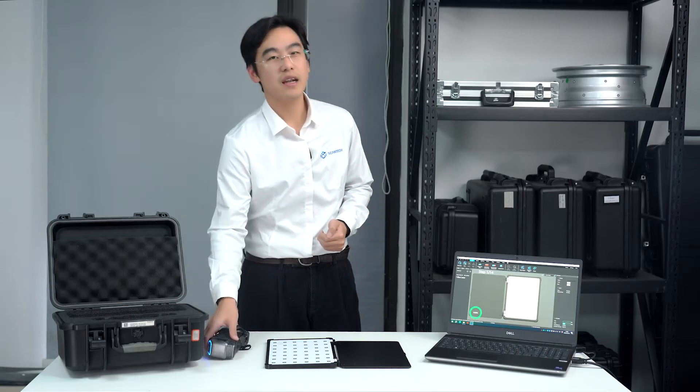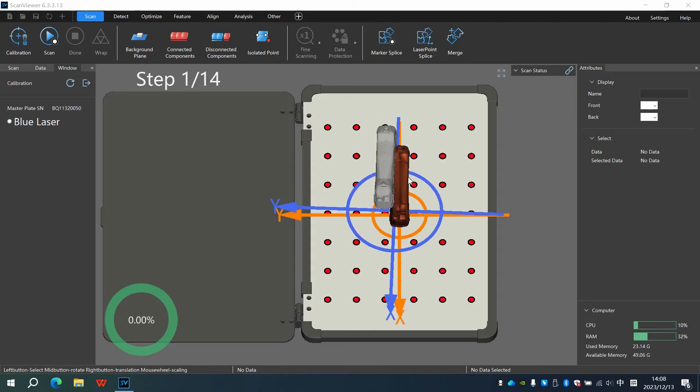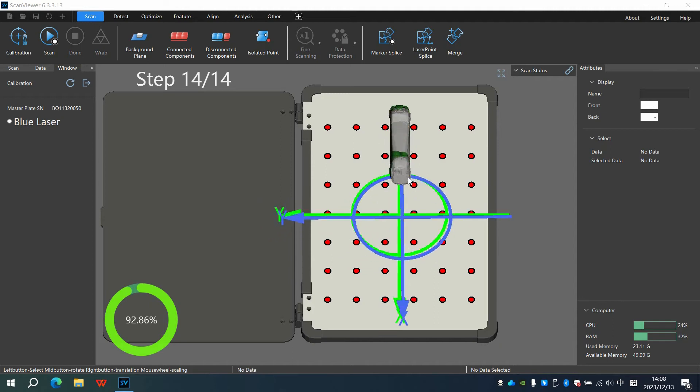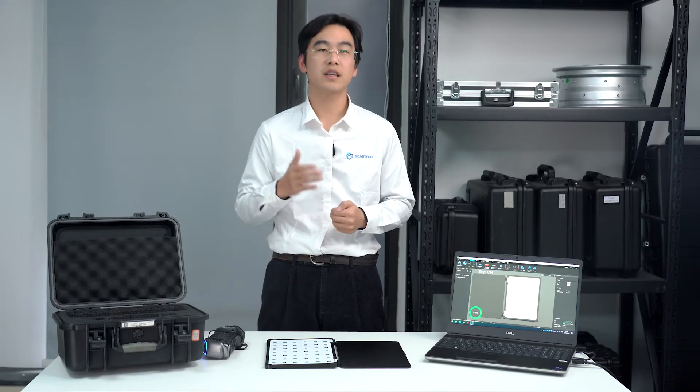Hold SimScan and we are ready to initiate the calibration process. Align SimScan with the X and Y-axis, following the on-screen prompts in ScanViewer that indicate the relative position of the scanner and master plate. With a slow and steady movement, you will complete the calibration.